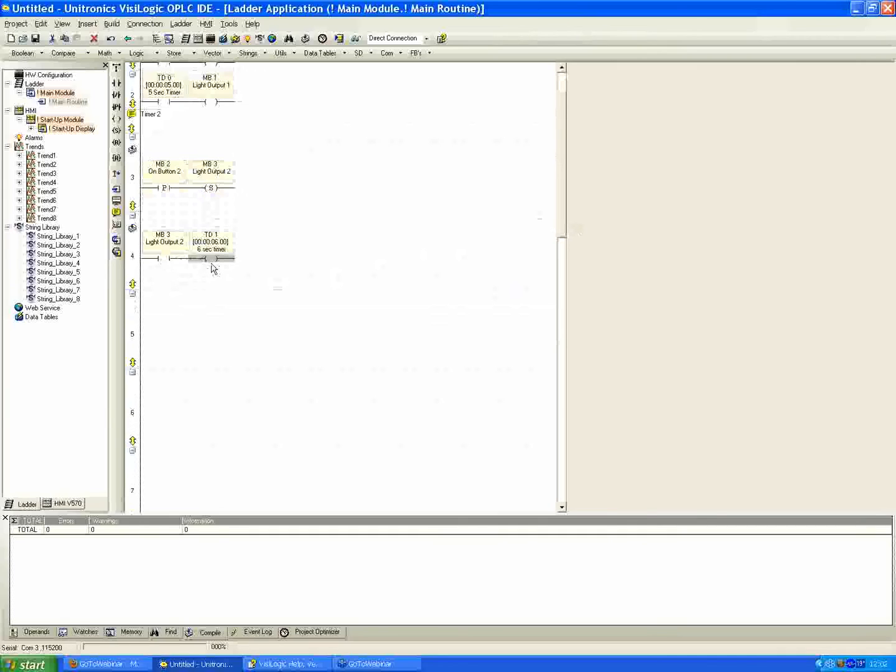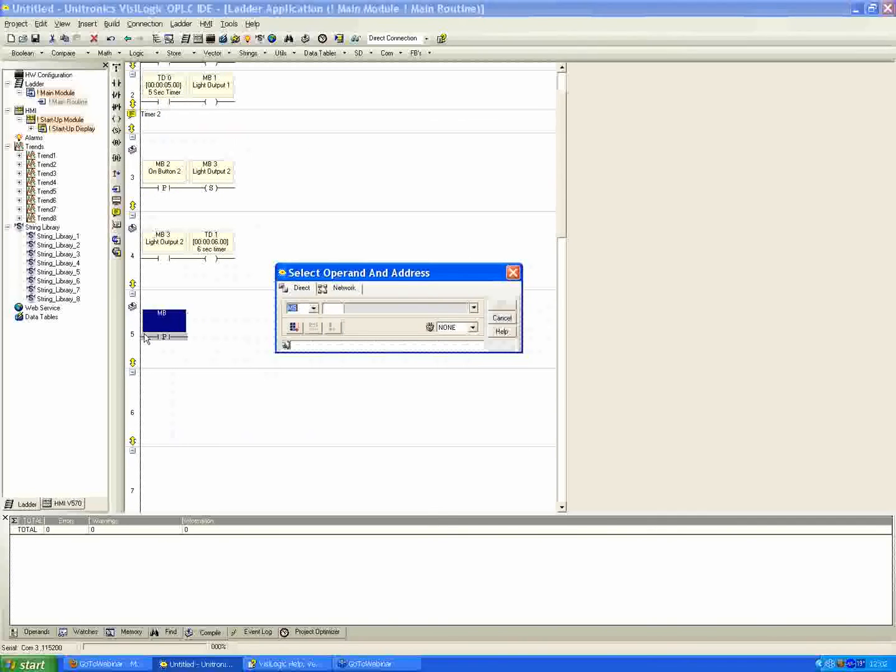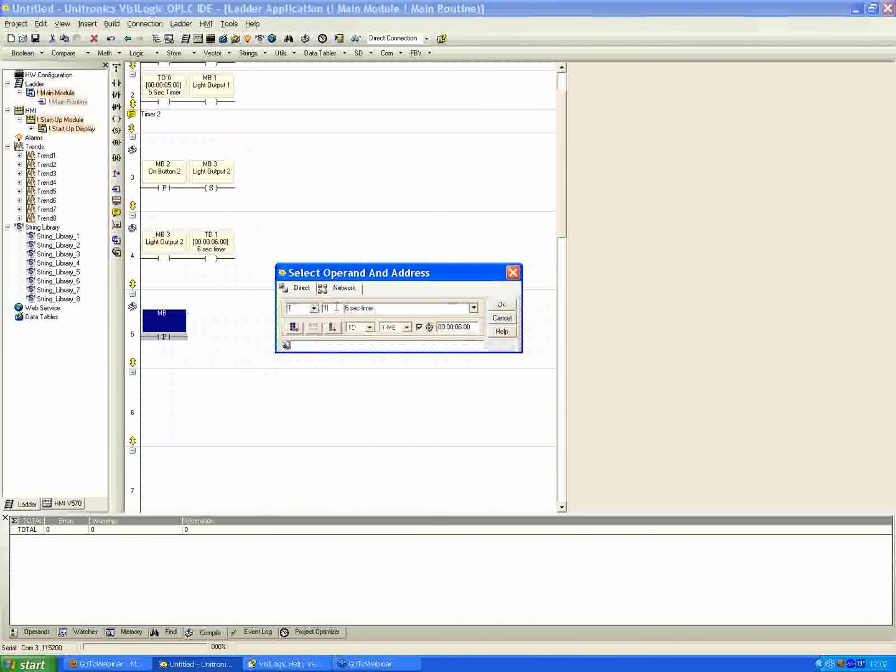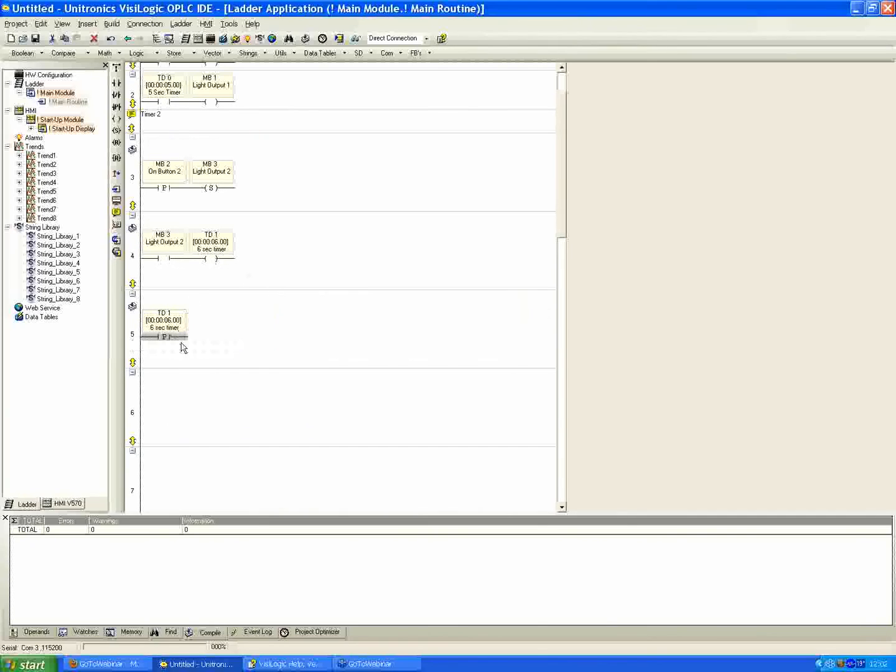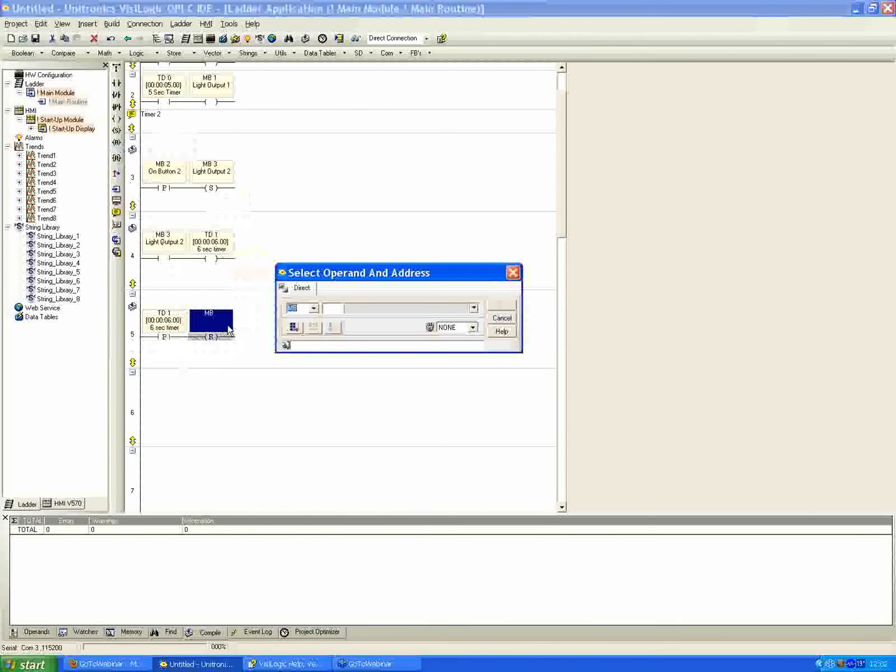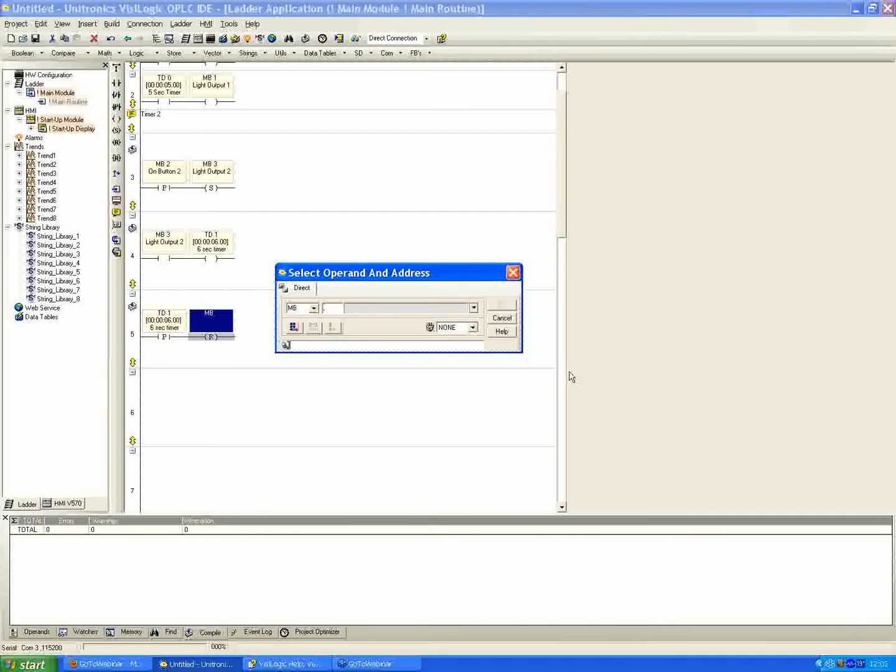So we're going to energize our timer here as long as the light is on. Now once the timer counts down, we will use a positive transition contact this time in the net right below. And here it's going to go to our TD1. Hit OK. So the timer is being energized. Once the timer is finished counting down from at 6 seconds, the internal bit will go high, which is going to be recognized in net 5 here by the positive transition contact. And what we want to do then is shut off our output. So we're going to shut off the light, which also therefore kills power to the timer.